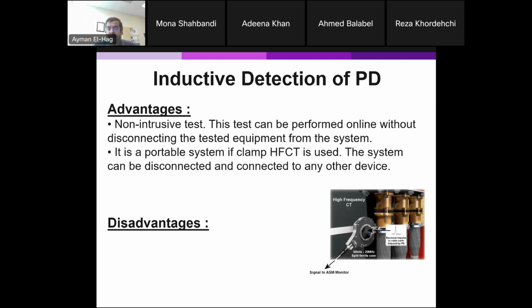Also, it can be portable if you have it in a clamp. So sometimes the CTs come in a clamp, so you can go and connect it to multiple types of connection points. Okay, if you want to go and scan different transformers, with the clamp you take it over there and put it there and keep monitoring, then move it to the second one, and so on and so forth. So that is another advantage, that you can monitor multiple units, not at the same time, which is one of the limitations. Or it's not easy to be done. You have to physically go and remove the current transformer, and connect it to something else.